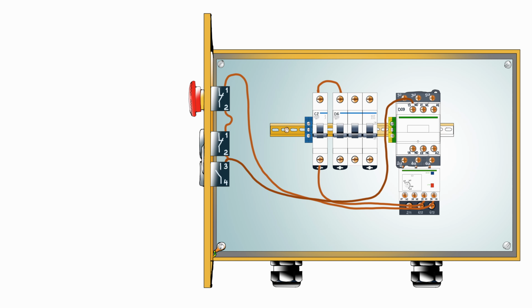And then from the bottom of our start button at 4, we connect another cable that is long that goes back to our contactor, and we connect it to 14. So this point here, 14, is also the same point with the contactor coil, which can be A1 or A2. So I would say just connect it to the one that's most convenient. 14, we connect it to the contactor coil, and the remaining point on the contactor coil, we connect it to our neutral, and that's it for our control circuit.